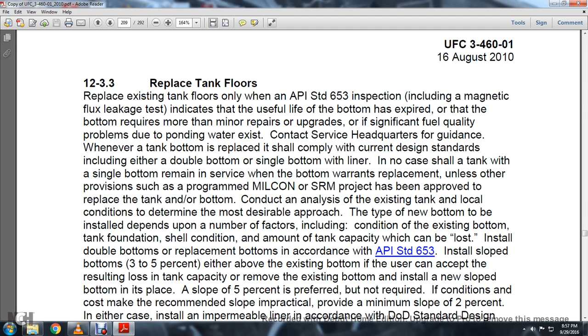In no case shall a tank with a single bottom remain in service when the bottom warrants replacement, unless other provisions are programmed, such as a Military Construction or SRM project that has been approved to replace the tank bottom. Conduct an analysis of the existing tank under local conditions to determine the most desirable approach. The type of new bottom to be installed depends on a number of factors, including the condition of the existing bottom, tank foundation, shell condition, and the amount of tank capacity which can be lost.